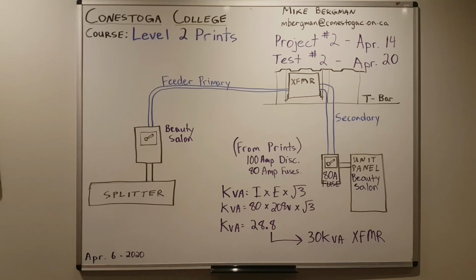Perhaps they get busier, they add more chairs, they add more personnel working in there. They pull out those 80 amp fuses, they put in 100 amp fuses, and that transformer will be able to supply the ampacity that unit requires. So look at the disconnect feeding the units from your prints, and then do 80% of the ampacity of the disconnect. So in this case, it's 80% of 100, so 80.